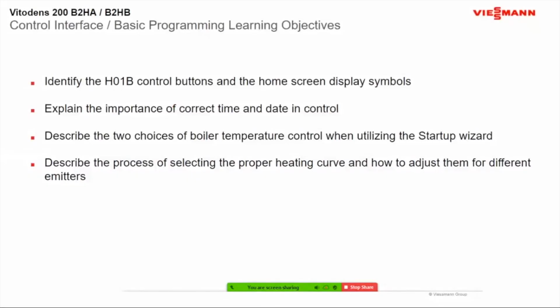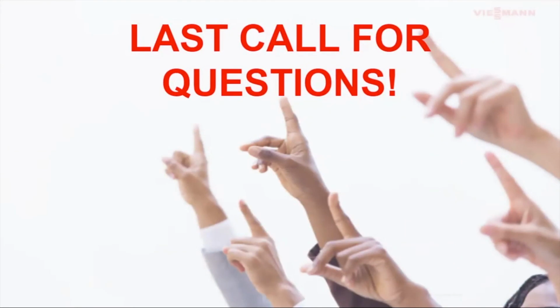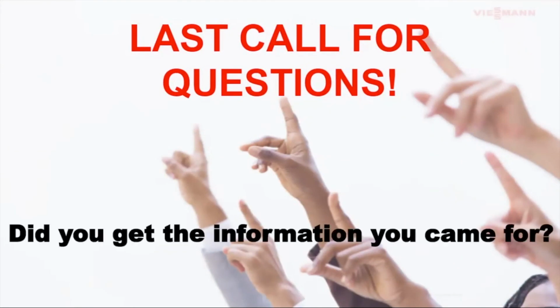So I'm sorry I ran a little longer than I should have here, but hopefully you got some information that you need. I covered pretty much all your screen displays. Remember the importance of the time and date, your fault code history, your time programs, your vacation mode, things to that nature. You can either do a fixed set point or do a weather compensation. So that's your difference between your boiler setups on your startup wizard there. And hopefully you learned a couple of things about your heating curve that might help you down the road as well. So we're kind of at the end of the presentation here.